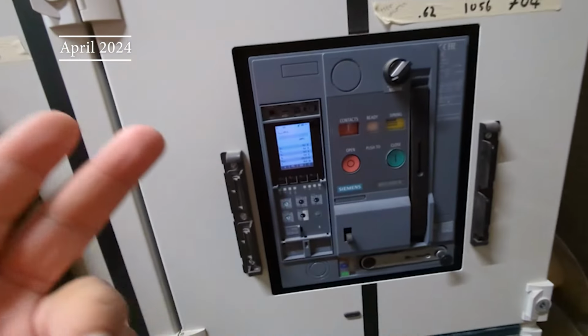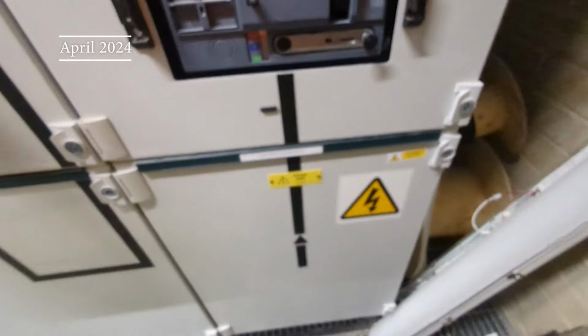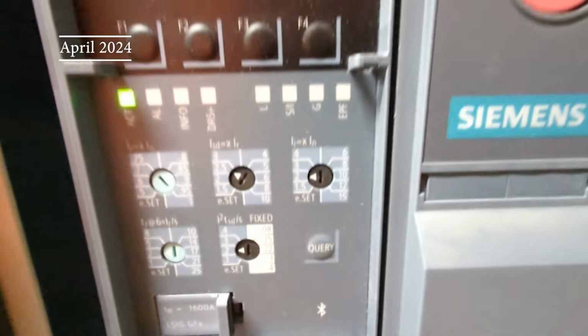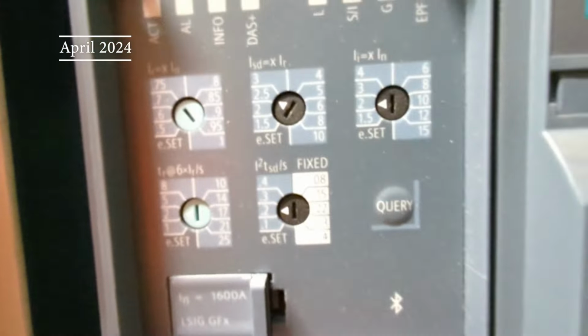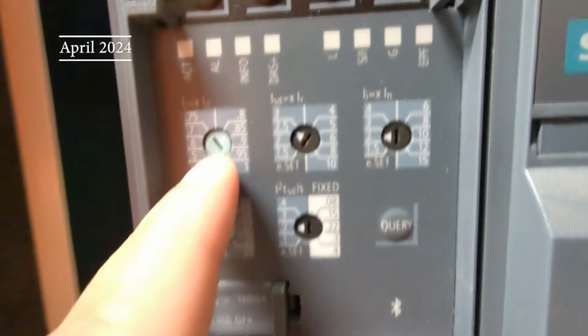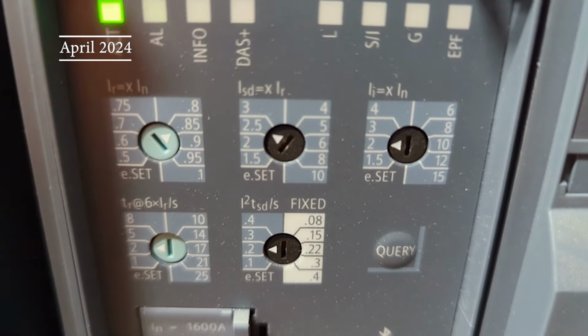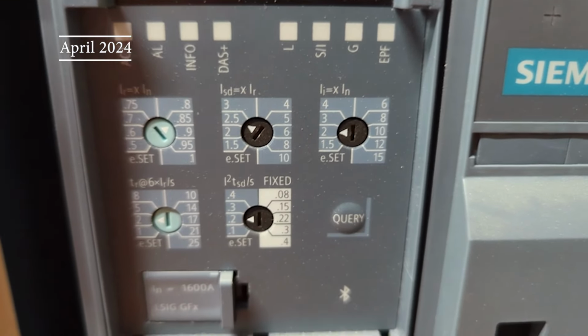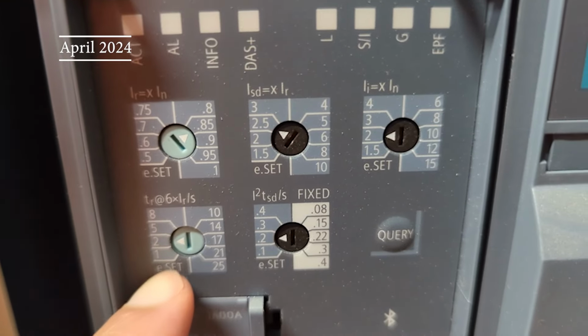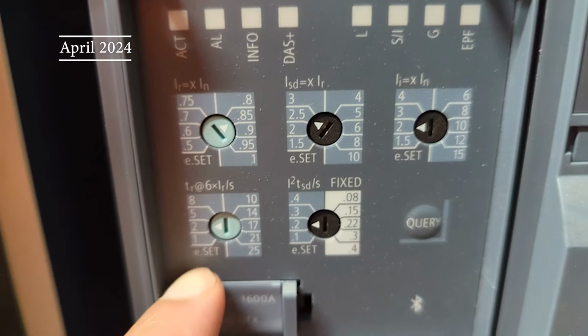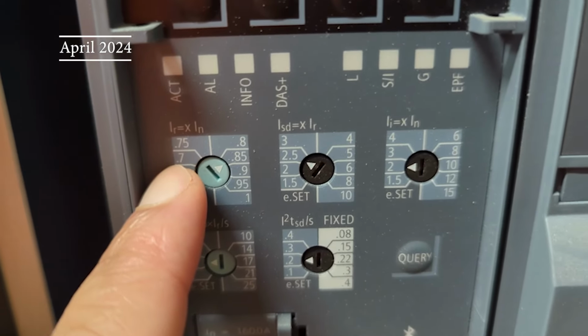What should be happening is the transformers get fed through the floor into here. This circuit breaker here is rated at 1600 amps. This should be blowing. If you don't know, I've got LSI settings here on the circuit breaker. To show you what they are, you've got IR, which is overload. This is the percentage that you want. If it's a 1600 amp breaker, then your IR setting there is 0.85, so it's 85% of 1600 amps, probably about 1300, 1400. And then you've got the duration at which it sustains that overload. Here it's 2 seconds, and then this should blow, which it's not at the moment.